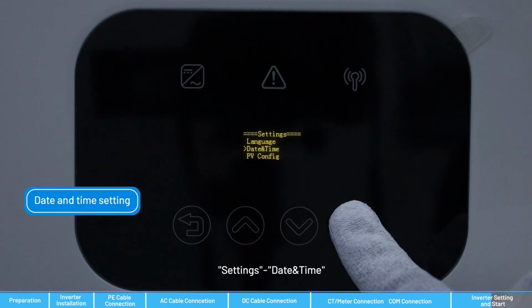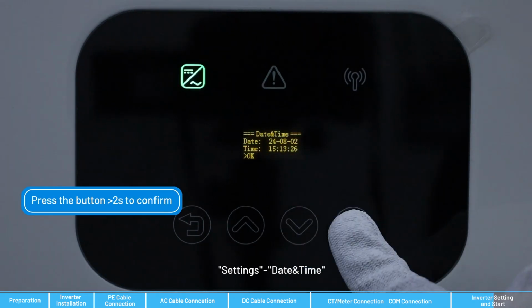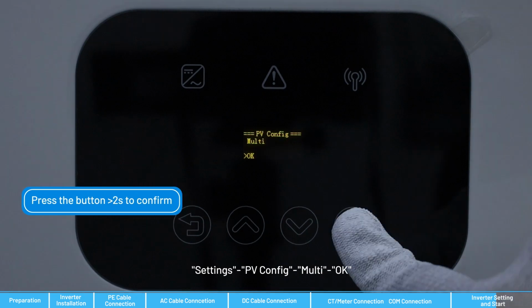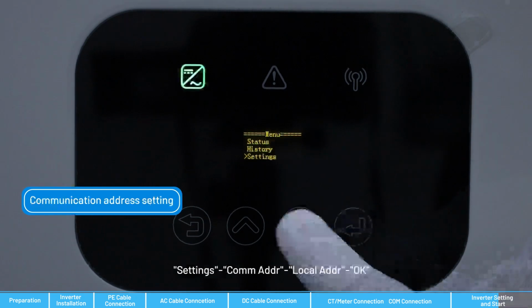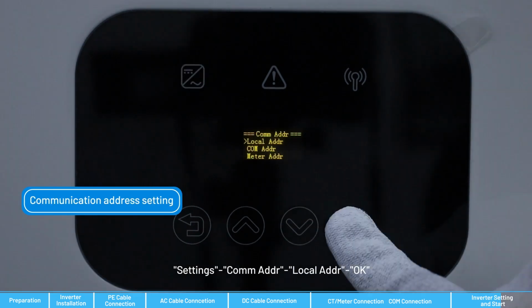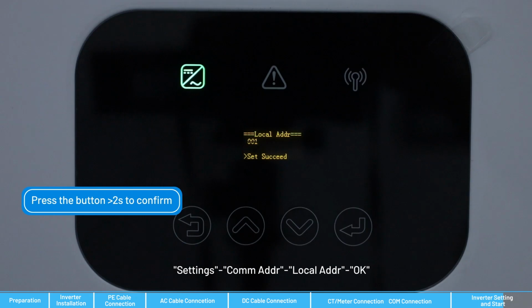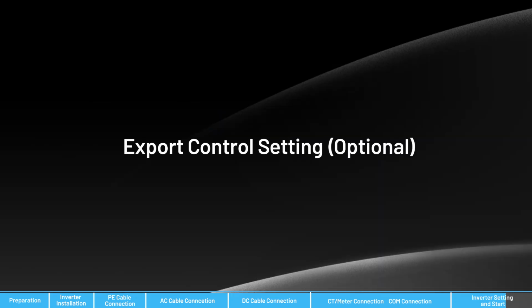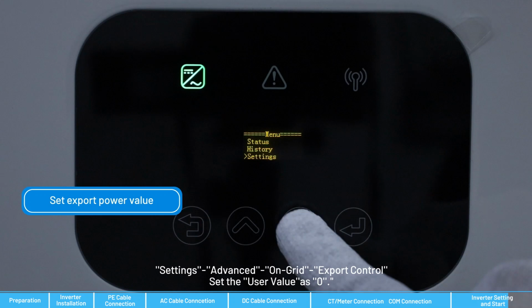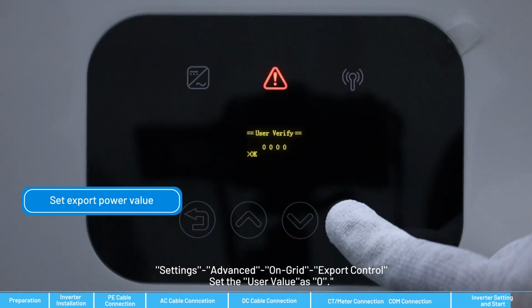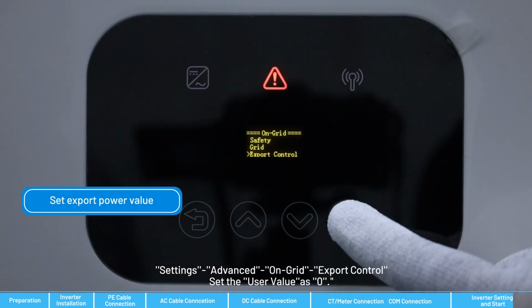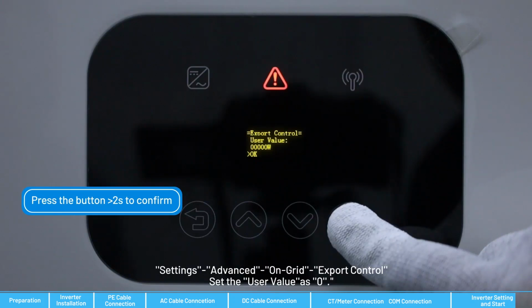Settings. Date&Time. Settings. PV config. Multi. OK. Settings. COM address. Local address. OK. Settings. Advanced. On grid. Export control. Set the user value as 0.